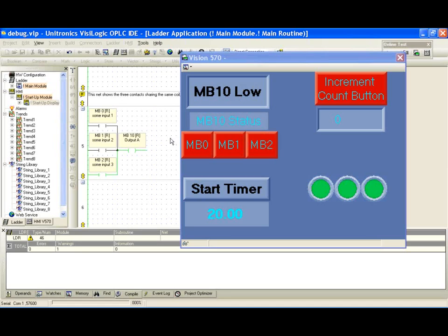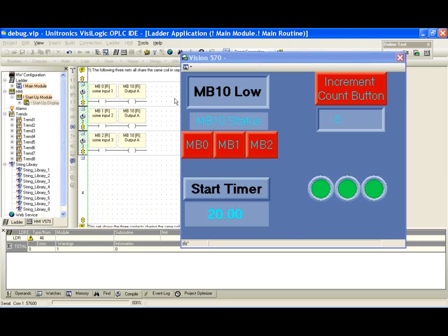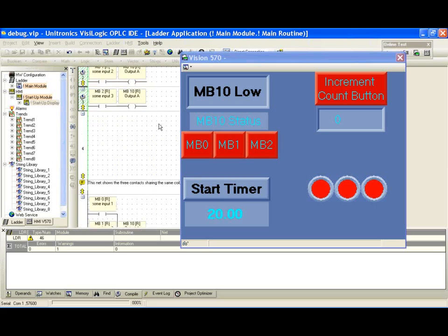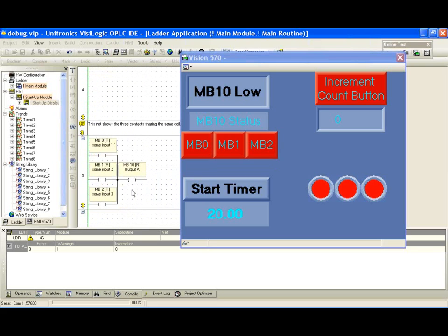Now this, I would say, is for a beginner especially, the first, simplest, easiest mistake to make. If we want to have several conditions all activating a similar output, we're going to say, okay, just running through the logic in our head, I'll have this condition, and then we'll have this output coil. And then I have another condition, and we'll have this output coil. It's very important to group these. Again, we've made a parallel network here with a single output. We're not battling each other. Everything is working together.